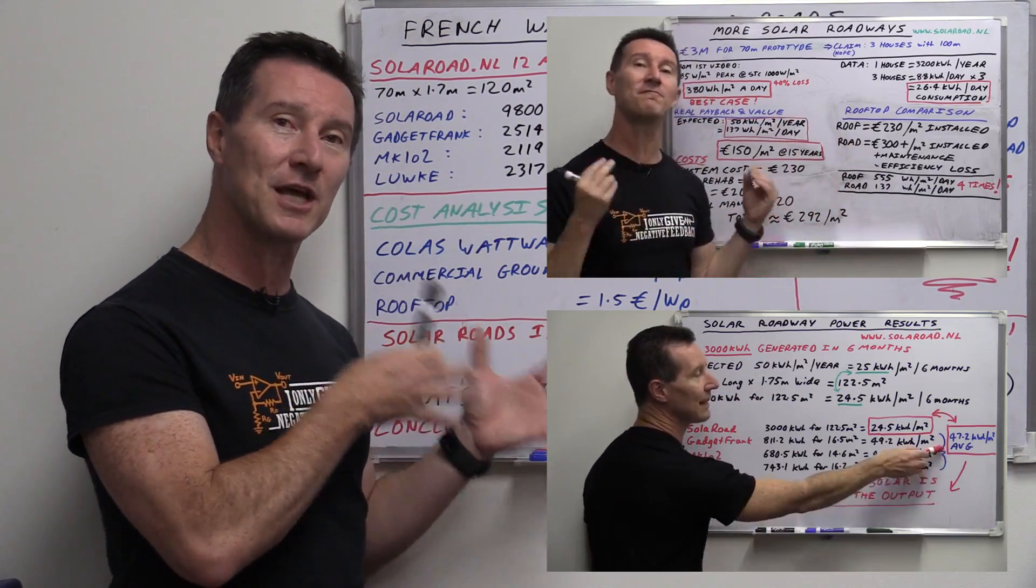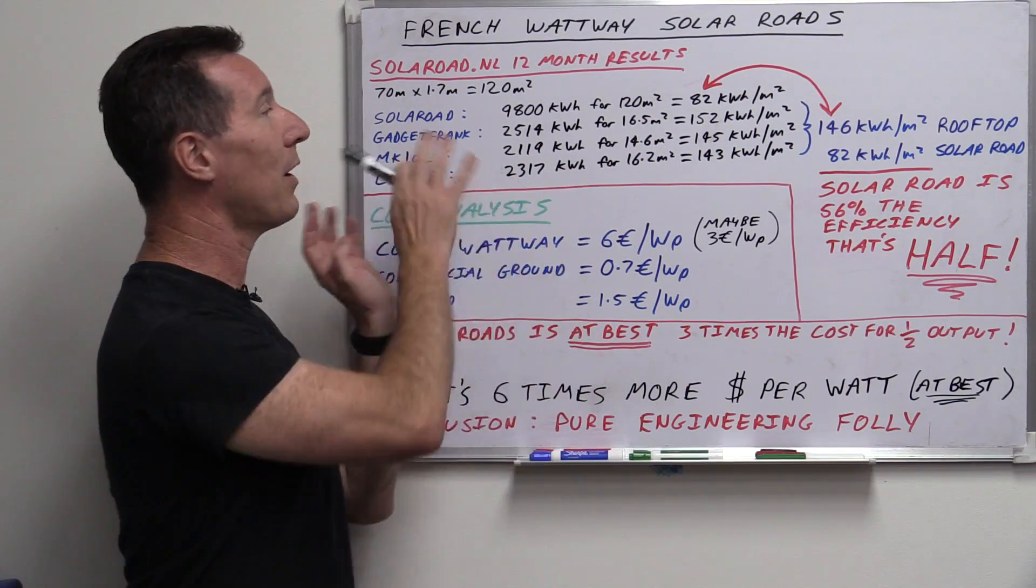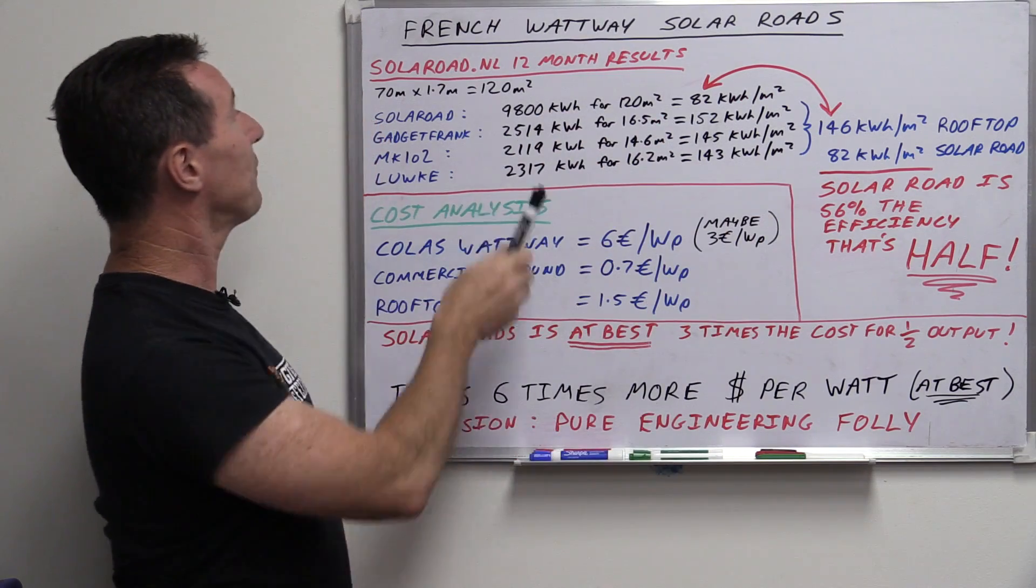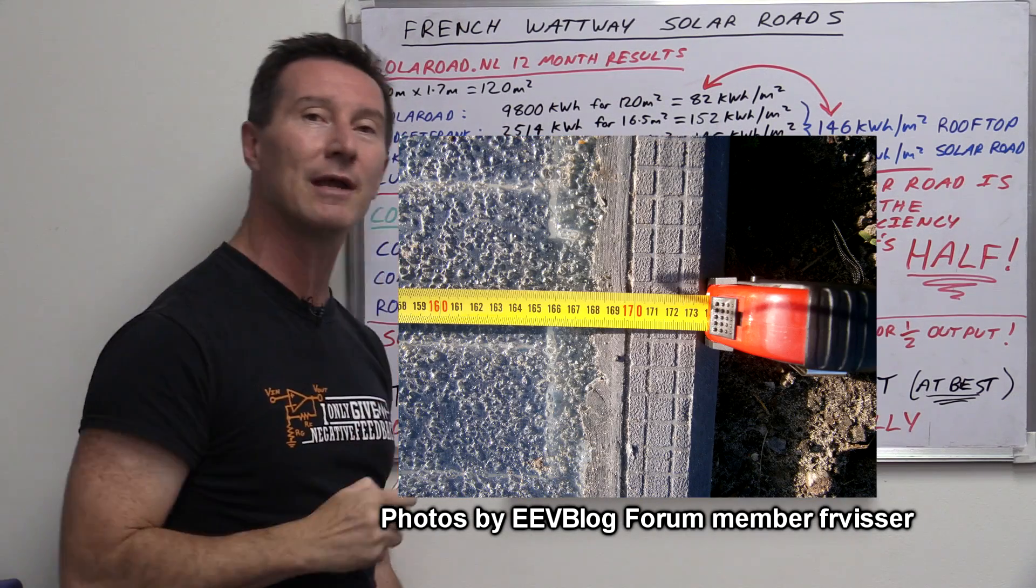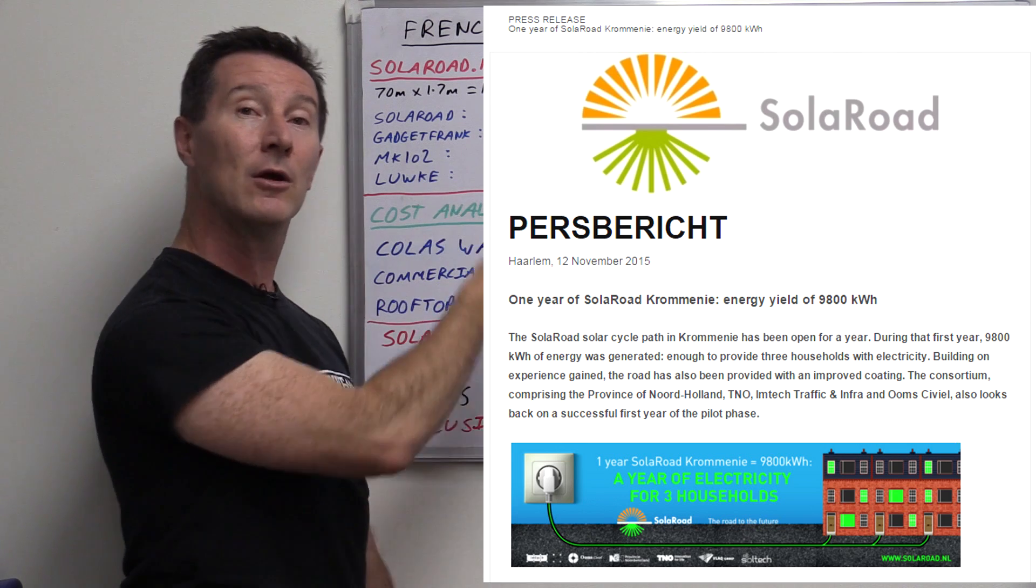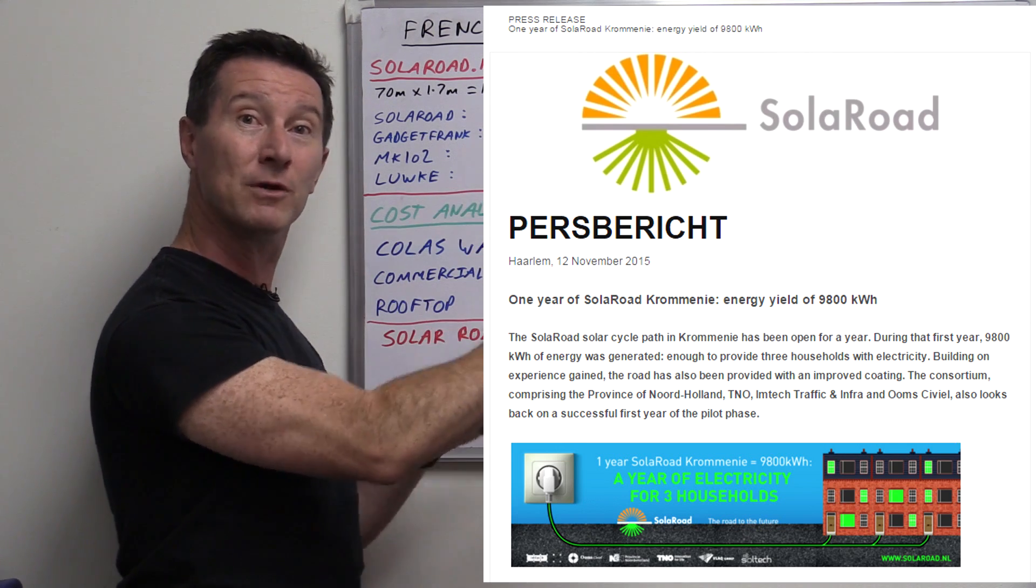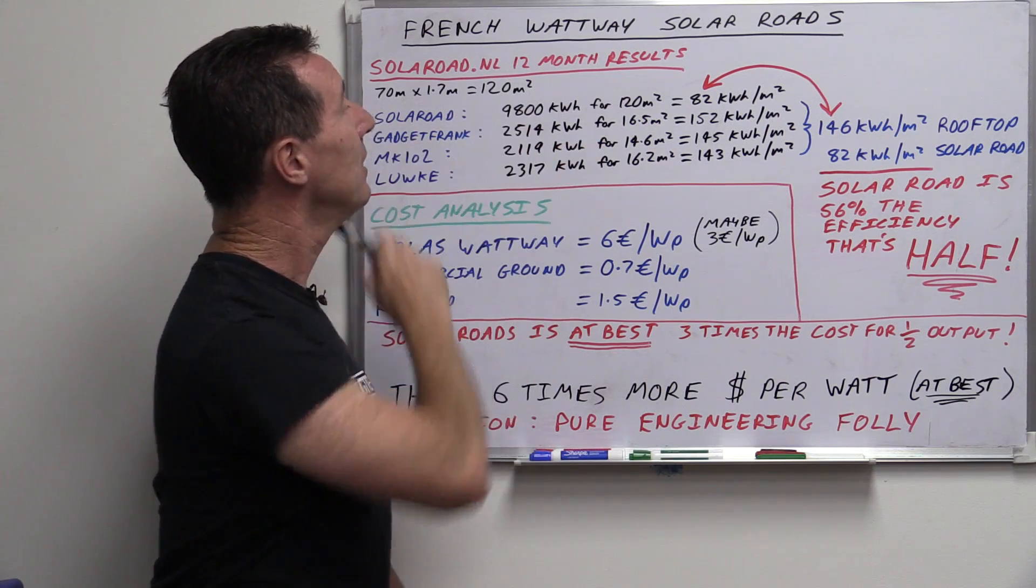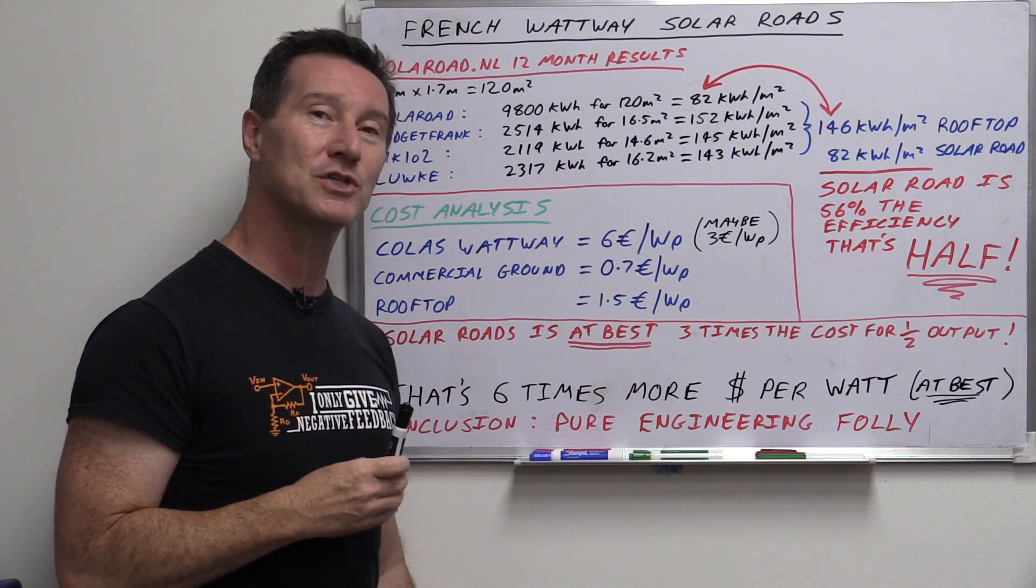Now we'll very quickly go back and just analyze the Netherlands project, the solarroad.nl one. We looked at the six-month test results, and some people said let's wait until we get 12 months. Well, we do have 12-month test results. The solar road project is a 70-meter strip by 1.7 meters for a total area of 120 square meters. They've said in a press release after one year, 9,800 kilowatt hours for that 120 square meters. That gives us 82 kilowatt hours per square meter.